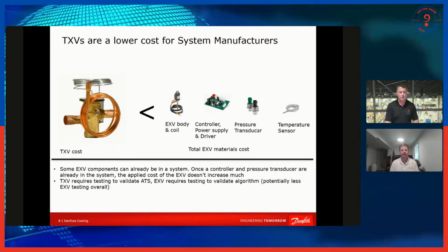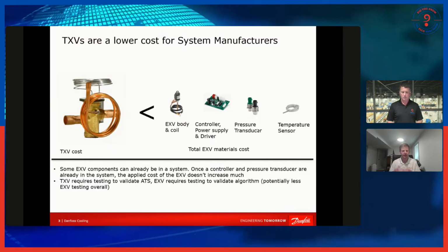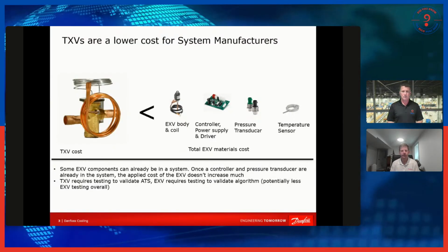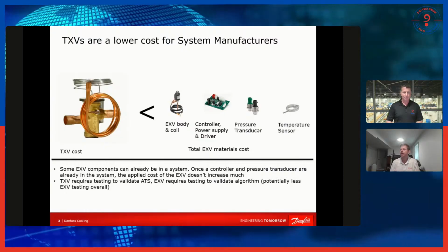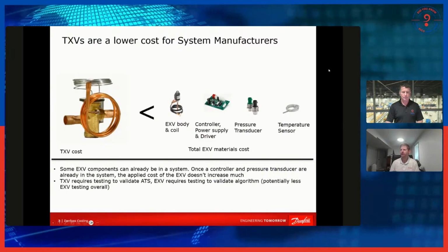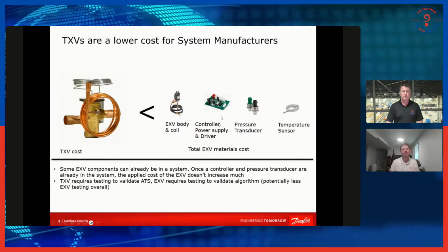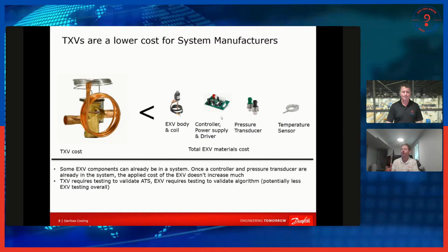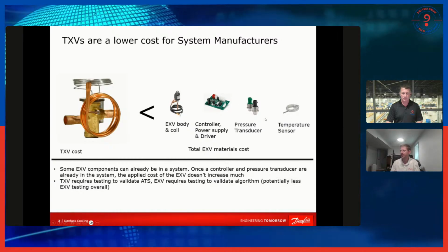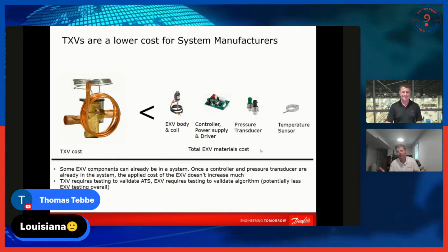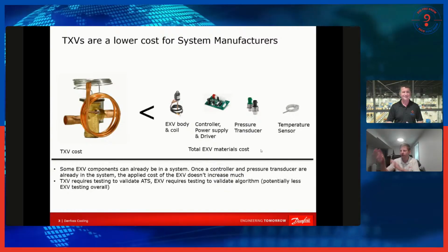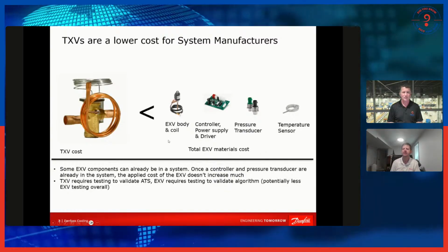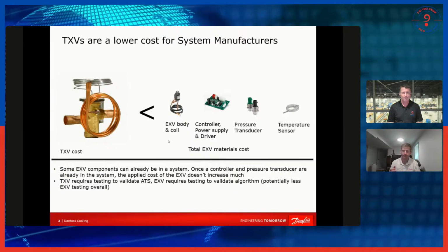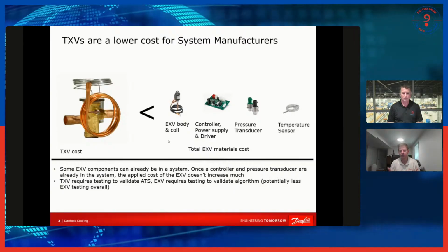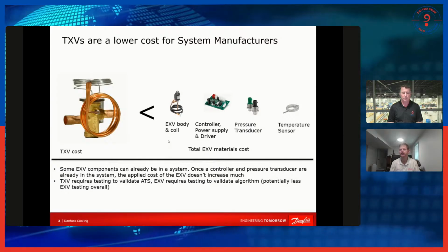So if you're going to use an EXV, it needs to be in a situation where you're able to take advantage of the advantages that it can bring you. And as time goes on, you might just see more EXVs because there's already going to be more electronics in the system. If there's more electronics, it makes some of these other costs go away. If there's already a pressure transducer to give a low suction pressure alarm, now you don't have to add that to the cost. And if all these electronics are already in there, it makes the cost of that EXV not so expensive, and it makes it an easier switch to make.